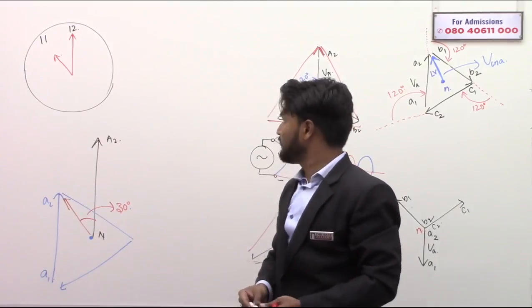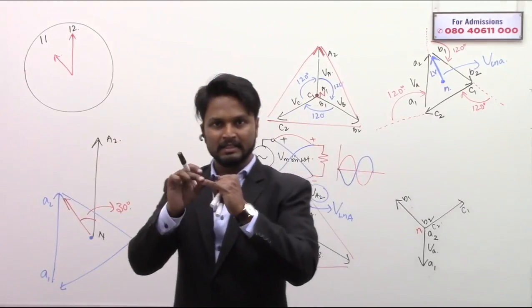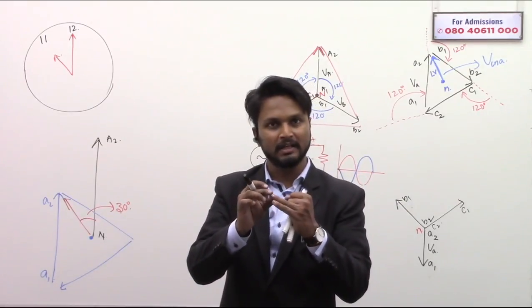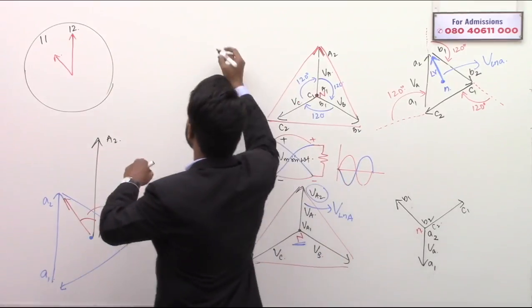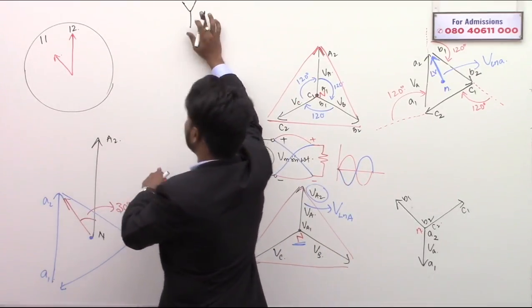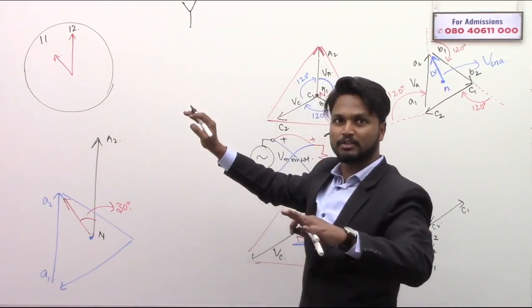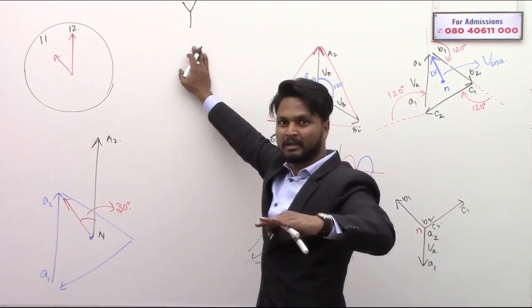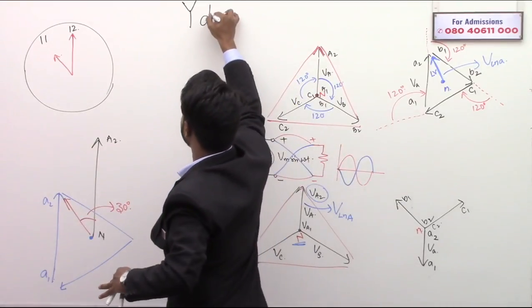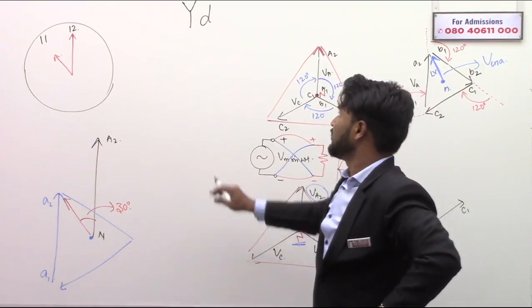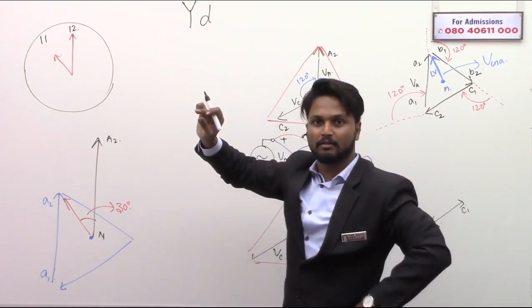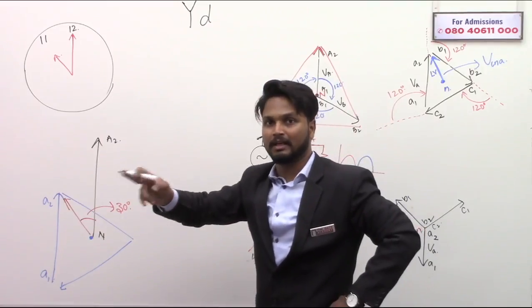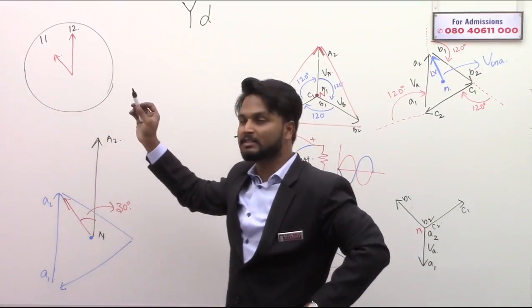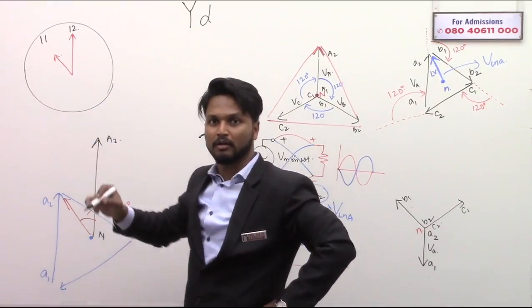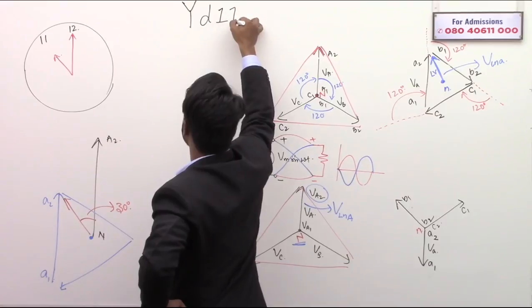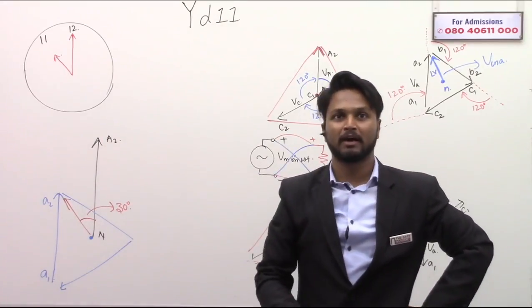It is YD11. The HV side is star connected, LV side is delta connected. HV side star connected means HV side you represent by capital letter -- you must know the nomenclature. HV side should be written with a capital letter. LV side is delta connection, so LV should be written with a small letter: HV star, LV delta, and the phase difference is like this, indicating 11 o'clock position, which means YD11 is the phasor group.